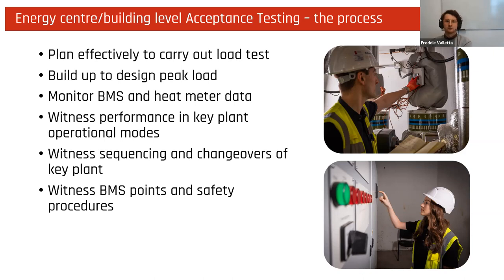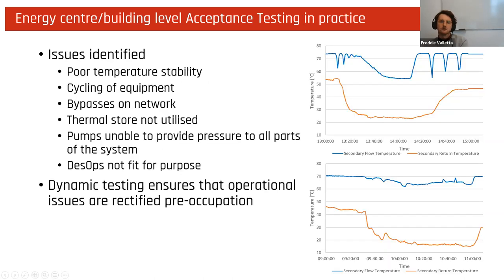I should say that Sula touched on, in her presentation, the idea of seasonal commissioning. And yes, again, this is when your BMS and heat meter data can be included to fully prove the system performance over a period of time. In practice, these are some of the issues that we've observed on site. As you can see, there's a whole range of issues from heat generation equipment to pumps and the network commissioning and also the controls as a whole.